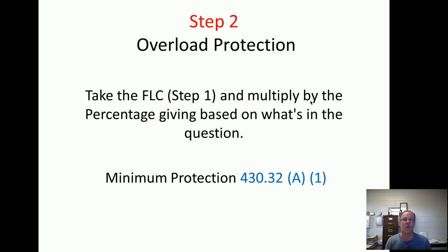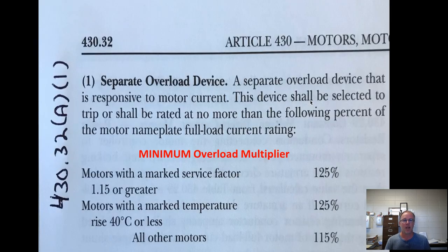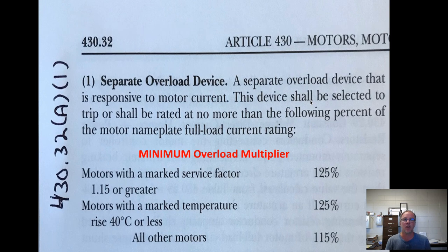We want to keep the motor from heating up. How do we do that? We control the amperage. So step two, overload protection — we take the step one full load current and multiply it by what 430-32A1 says for minimum protection. It says a separate overload device, responsive to motor current, shall be rated at no more than the following percent of the motor nameplate full load current. If the nameplate is available, we use it; otherwise we go by horsepower and voltage.